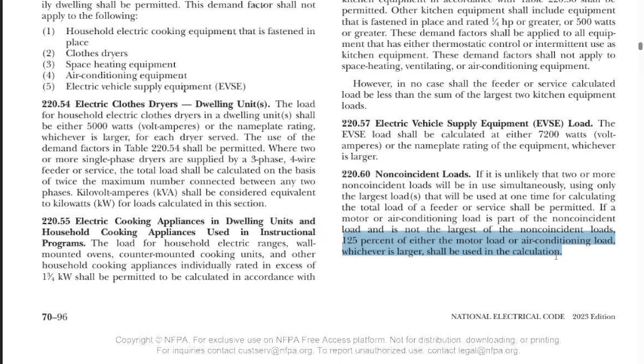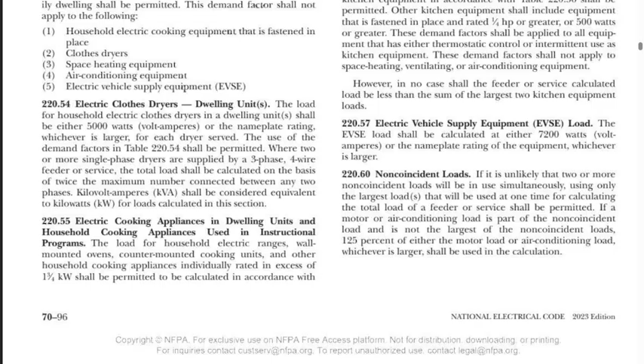But if the air conditioner is not the bigger one of the two, then first we run the percentage increase. The last sentence, if we didn't highlight it yesterday, make sure you highlight it now: highlight 220.60 non-coincidental loads and that last sentence, which sums it all up—125% of either the motor load or air conditioning load, whichever is larger, shall be used in the calculation.